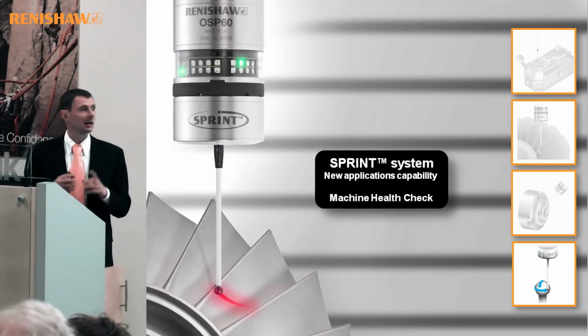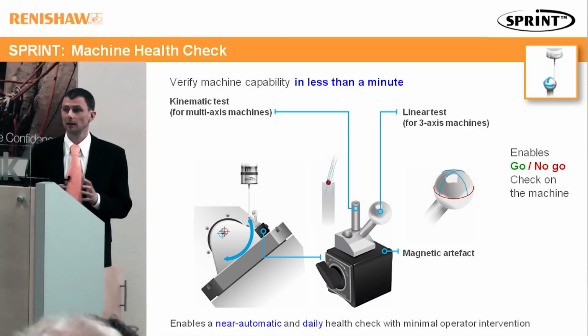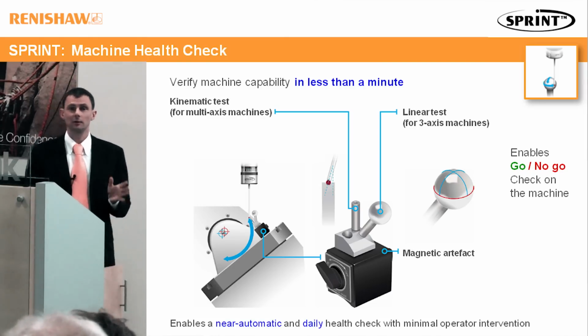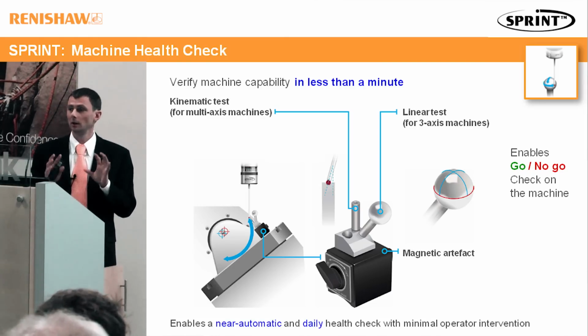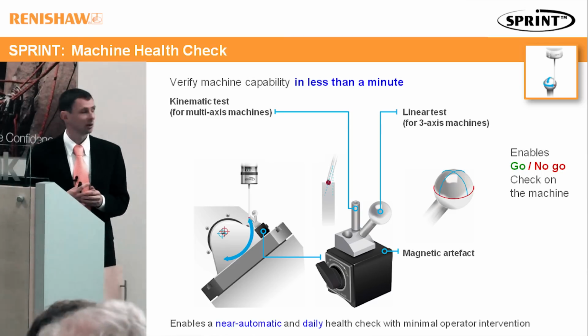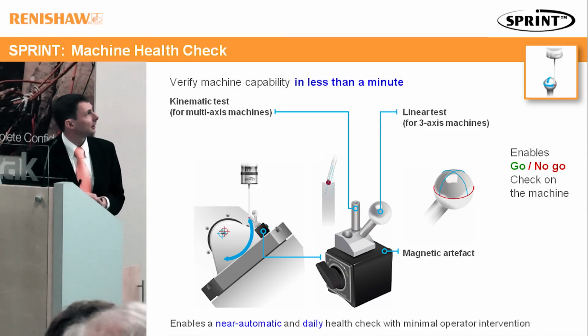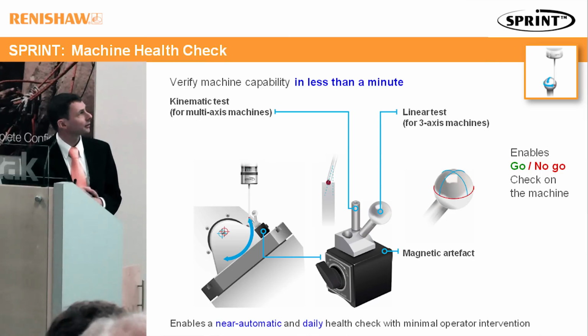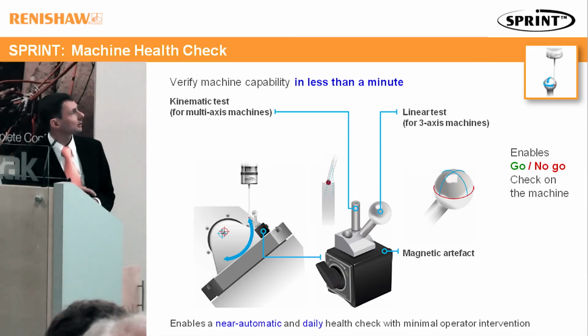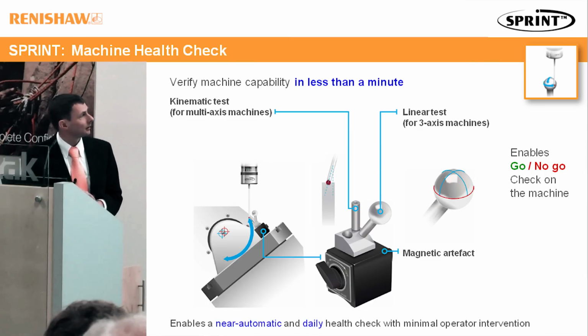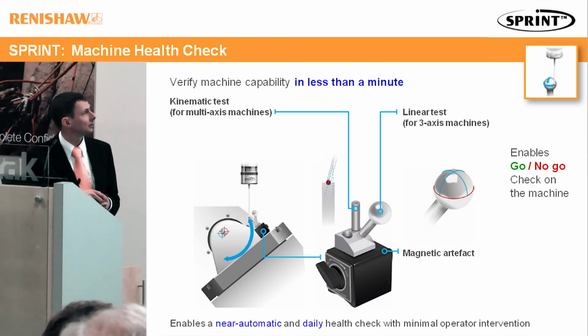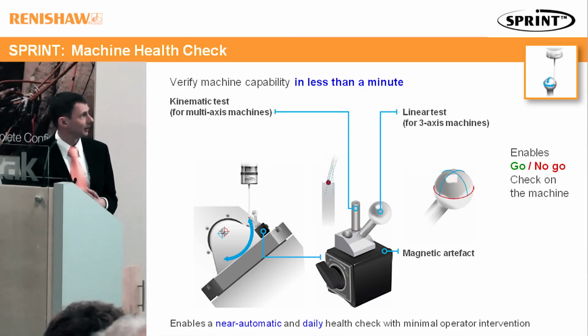Thirdly, the Machine Health Check Toolkit. This allows us to verify machine capability in less than a minute. It's designed as a very quick and simple go, no-go check prior to cutting a part. It consists of 2 tests, one for 3-axis machines and one for multi-axis machines. The test consists of having a magnetic artifact mounted on the machine with a known sphere for the 3-axis test, and then this cylinder with a cone drilled into the top of it for the 5-axis test.